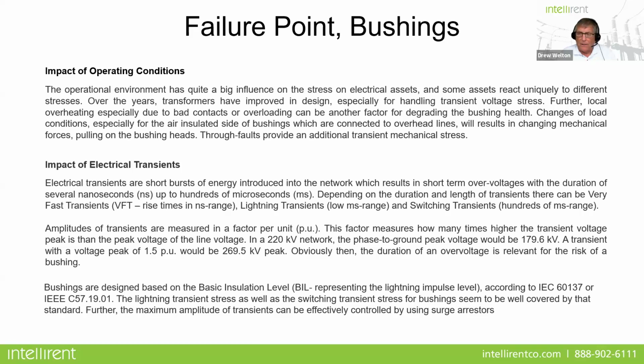We talked a lot about, I think not last time, but the time before that, the importance of through fault monitoring on transformers, because through faults that go through the transformer will put a lot of mechanical stress on the windings and the physical structure of the transformer. Well, the same is true for your bushings, and monitoring through faults. It's interesting because pretty much every new digital relay system has the ability to monitor through faults. What I find in the industry is very common that people don't enable this or pay attention to it. And it really should be something that you should be paying attention to.